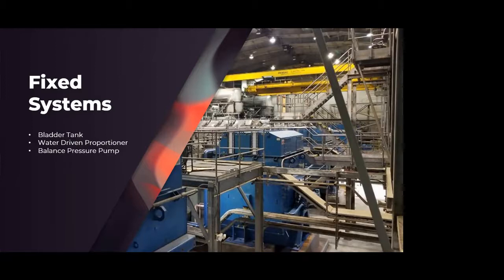It was 600,000 square feet. They were 3 racks high with their storage, wanted to go to 4 racks high. Code called for a secondary high expansion foam system. Goodyear says we don't want that because, geez, if the fire doesn't get the tires, the high expansion foam system will ruin them anyways. And so we put together a proposal, went to the authority having jurisdiction, which was the fire marshal in Memphis, Tennessee, and got the approval. So that's the only balanced pressure pump system that we have in place at the time. But that was 4,000 gallons of F500 that's proportioned in at 1%, protecting 600,000 square feet of rubber tires in Memphis, Tennessee.